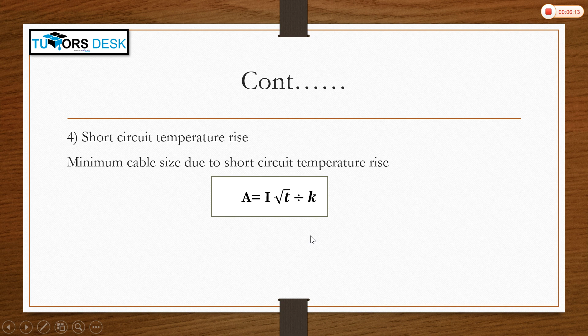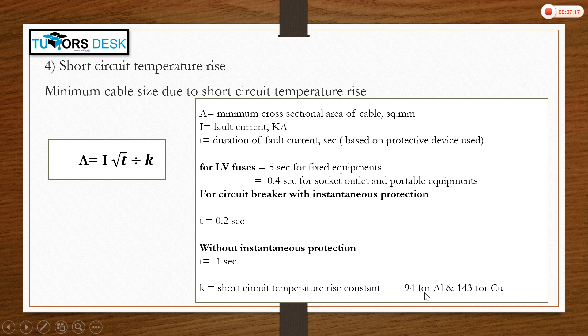For LV fuses used as a protective device, for fixed equipment the duration of fault current is 5 seconds, and for socket outlets and portable equipment it should be 0.4 second. If we are using a circuit breaker as a protective device, the duration of fault current is 0.2 second. If we are using a circuit breaker without instantaneous protection, that is relays like IDMT relays, then the duration of fault current is 1 second. And K is the short circuit temperature rise constant, which is 94 for aluminium and 143 for copper.